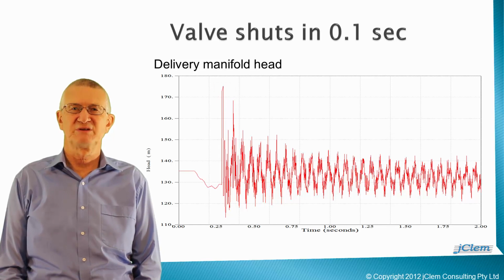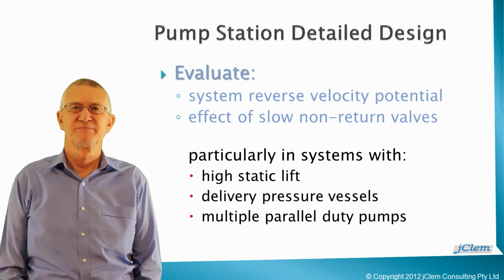Still not perfection, yet it might be in the range of acceptable loads on the valves, piping and fittings from a pressure rating and maintenance perspective. Whether it is acceptable or not will depend on the client's mechanical design standards.